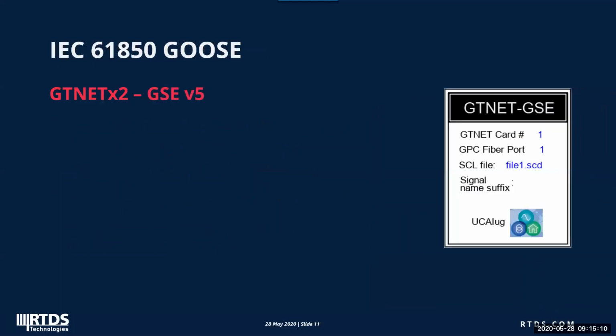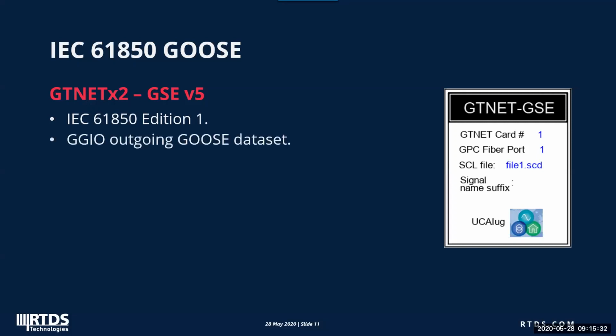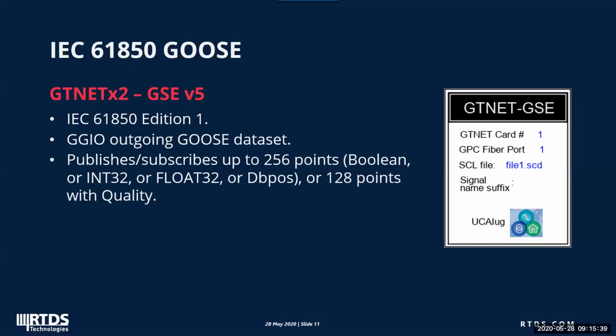So next, let's have a better look at the GSE and SV models. There are 3 GTNET GSE components available in the protection and automation library: V2, V5, and V6. We'll just highlight V5 and V6 today. The V5 component supports edition 1 of the standard and logical node GGIO for the outgoing GOOSE dataset. It can publish and subscribe up to 256 points of data types in either Boolean, integer 32, float 32, or double bit position. If quality information is required, then the number of points supported is halved. Up to 4 GOOSE messages may be published, and up to 16 GOOSE messages may be subscribed.